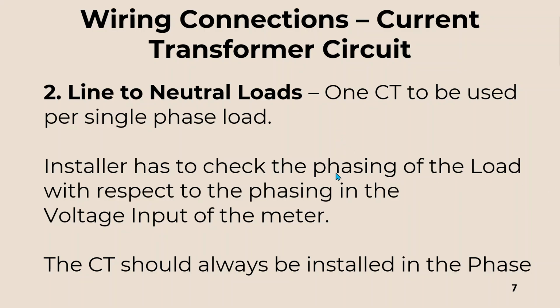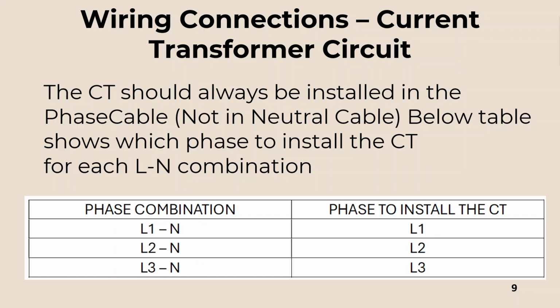Next are line-to-neutral loads. As with line-to-line loads, you need only one CT to measure each load. Same procedure: the installer has to check the phasing of the load with respect to the phasing in the voltage input of the meter. The CT should always be installed in the phase line of each load, not in the neutral. The procedure for identifying the phase of the line is the same as what we have shown before. Using a voltage tester, connect one of the leads to the meter voltage input terminals, and the other lead to the terminal of the circuit breaker where you are installing the CT.